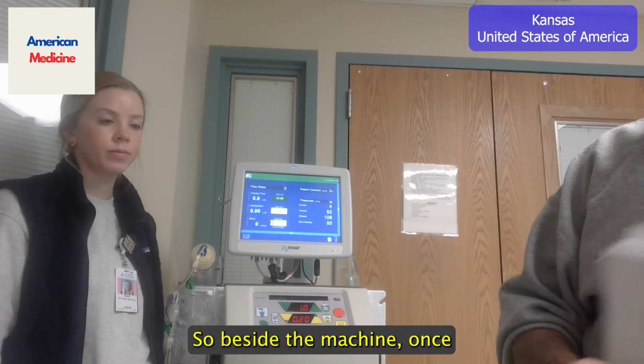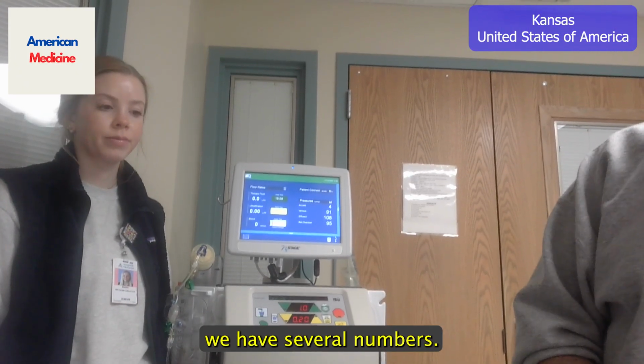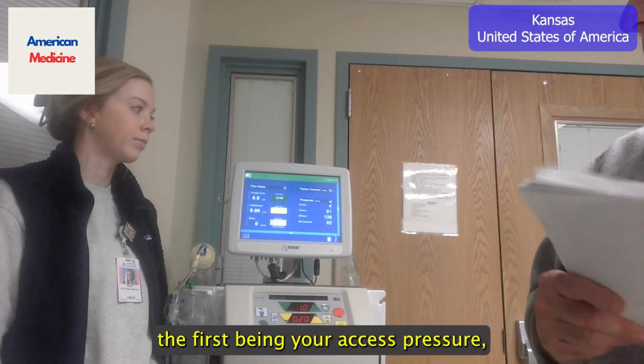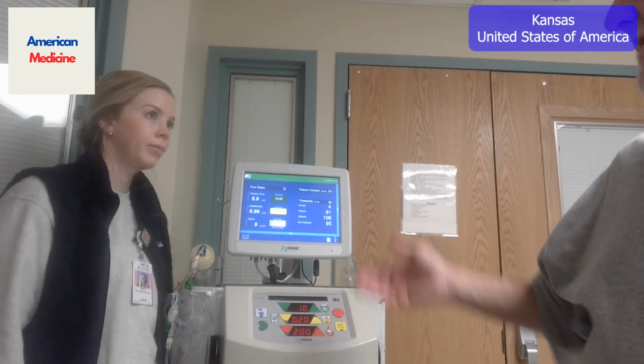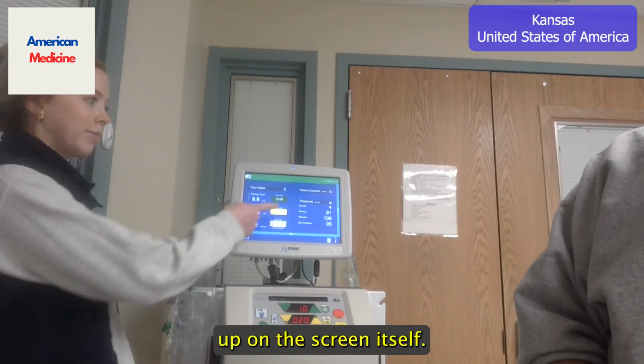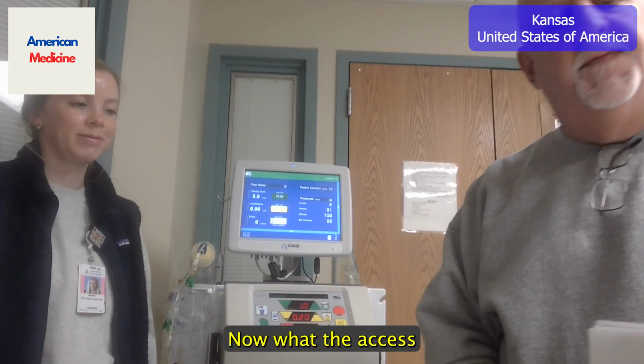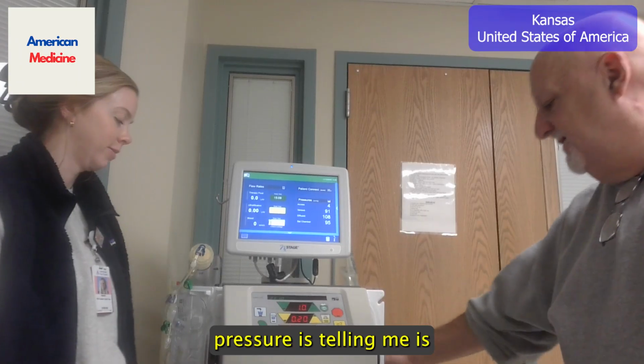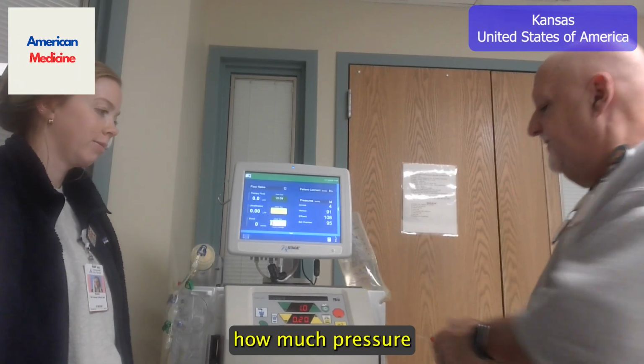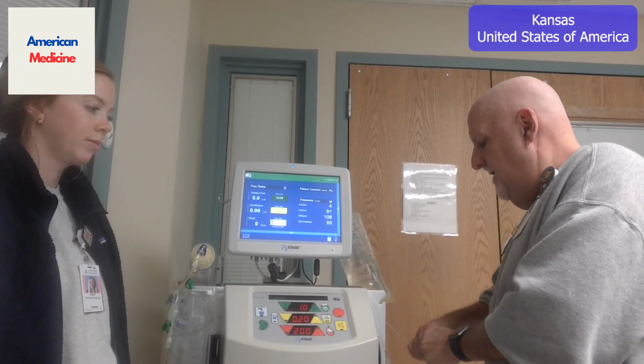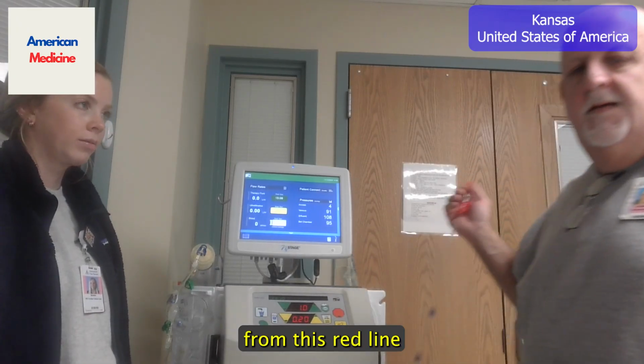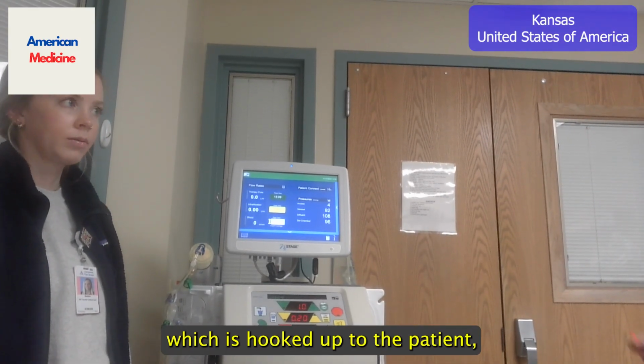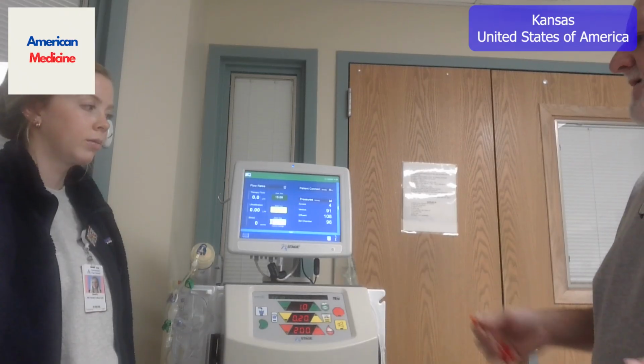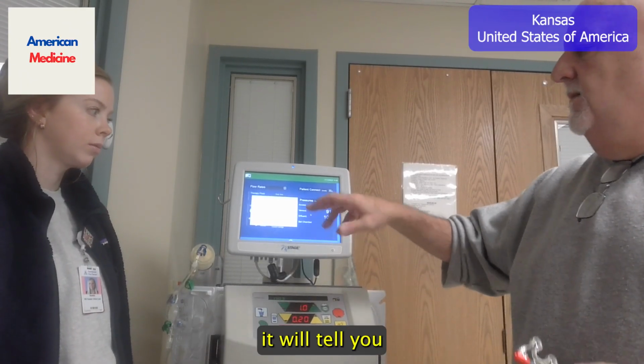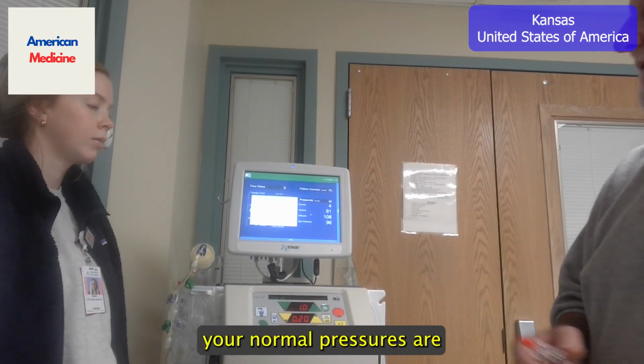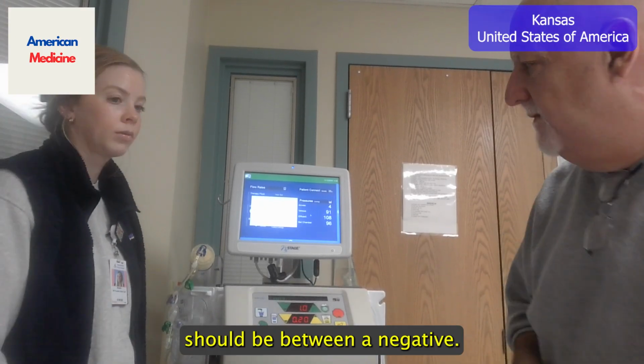So besides the machine, once the machine's up and running, we have several numbers we want to look at. The first being your access pressure, which is up on the screen itself. What the access pressure is telling me is how much pressure it's taking to get from this red line, which is hooked up to the patient, to the machine itself.